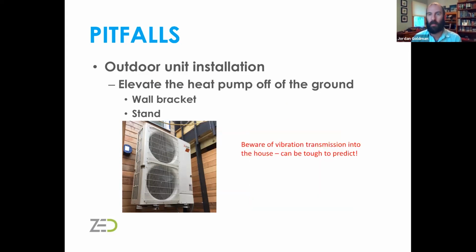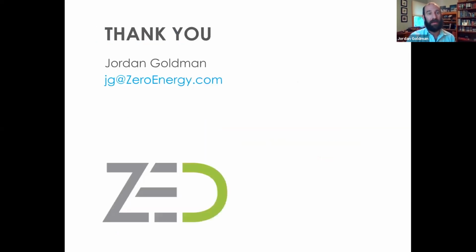I have stopped doing the wall bracket because I've gotten too many complaints about vibrational noise transmitting into the building, and it seems to be not too predictable as far as what houses it's going to be a problem in and what houses it won't. And it's really difficult and a pain to move this off onto a stand after the fact. So I just put them on a stand. And that's all I got.